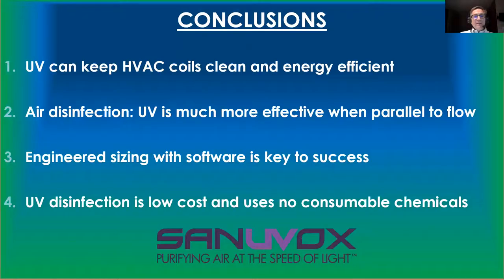So in a nutshell, and I'm open for questions after, UV is really a proven method to keep the coil clean and energy efficient by removing the biofilm. If you provide the right dosage, air disinfection is so much more effective when the lamps are installed parallel. Some people I've seen have tried to do it otherwise. Yes, it works, but it's like riding with a square wheel. It needs to be engineered, of course, you need software, you need to do it properly. So many times I've heard, oh yeah, we tried UV, it didn't work so well, we're deceived. Well, that's probably because it was misapplied.